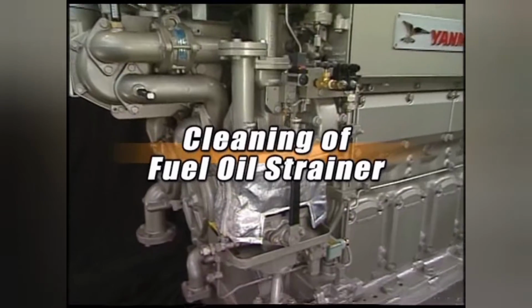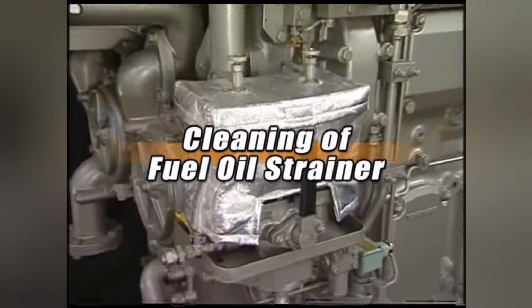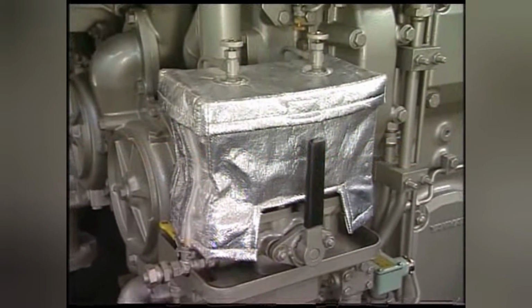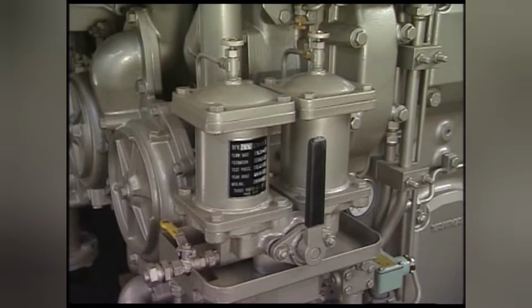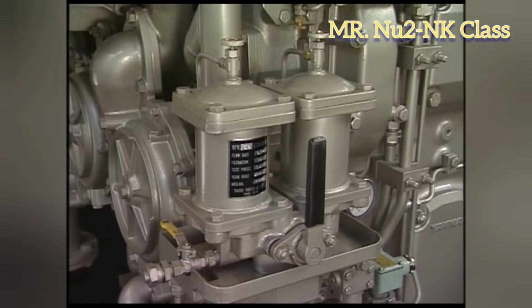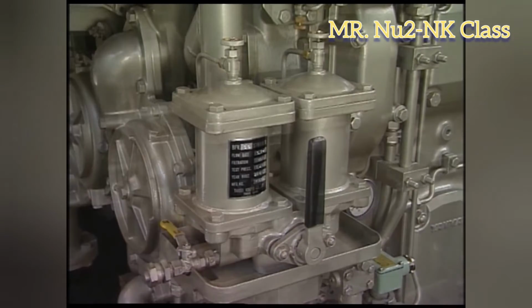Next, I will explain how to disassemble and clean the fuel oil strainer. There are two units of the same FO strainers on right and left side respectively, and they are used with fuel oil, filtering the elements on both sides during the engine operation. When you disassemble and clean them during the engine operation, conduct the work one by one according to the following procedure.